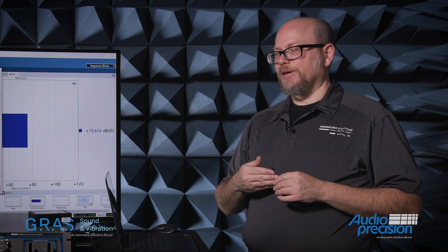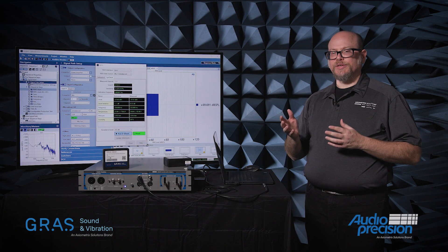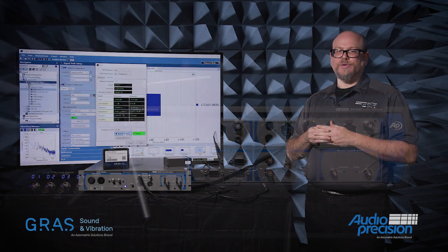SysCheck 2 is supported in Audio Precision's version 7 of our APX500 software, and it's supported using any of our analyzers with a CCP, or Constant Current Power Measurement, microphone interface. That includes the APX1701, the APX517, or any of our other analyzers when combined with a 1701 or one of the newer GRAS Type 12 BA, BB, or BD microphone power supplies.